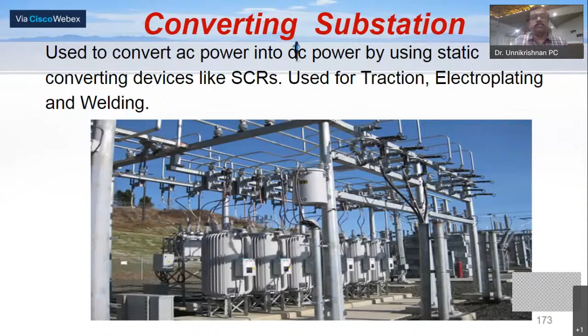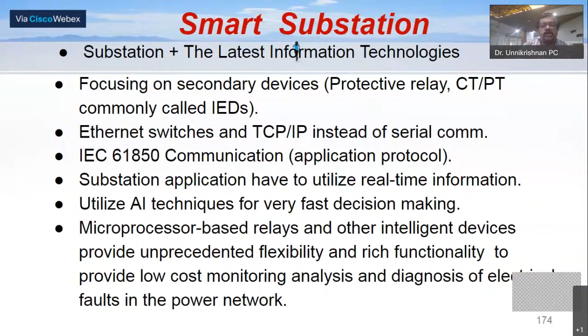Now we come to a smart substation. What is a smart substation? A smart substation is a traditional substation plus IT support, the latest information technologies. In smart substations, we use intelligent electronic devices (IEDs) as secondary devices, all protective relays, CTs, PTs. We use TCP/IP instead of serial communication, and the application protocol is IEC 61850, the latest application protocol. Some substations use the latest artificial intelligence techniques for fast decision making, so most of the relays will be microprocessor based or intelligent devices.